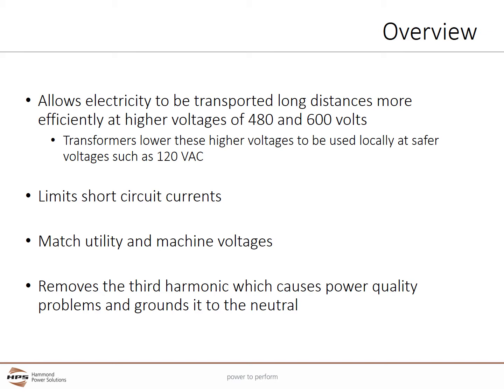Isolation transformers limit short-circuit currents during the event of a fault to improve the performance of fuses and circuit breakers. Transformers can match utility and machine voltages, and transformer taps can fine-tune the local voltage. Transformers with a Y secondary can remove third harmonic currents, which cause power quality problems, and ground these currents to the neutral.